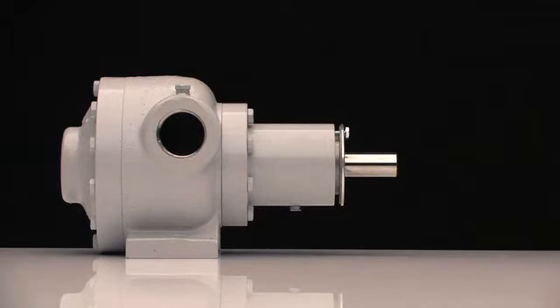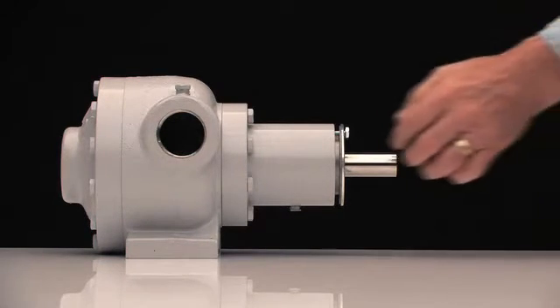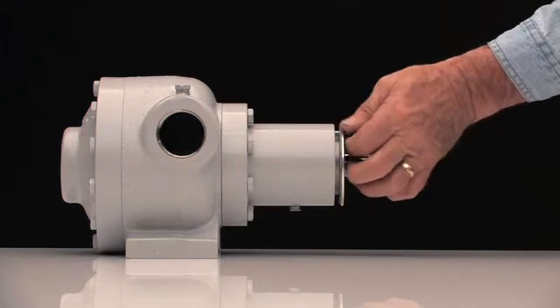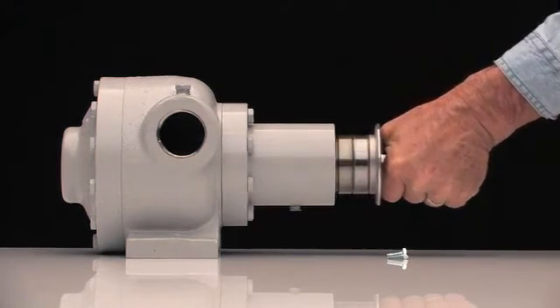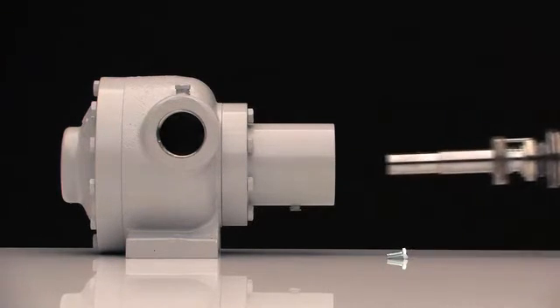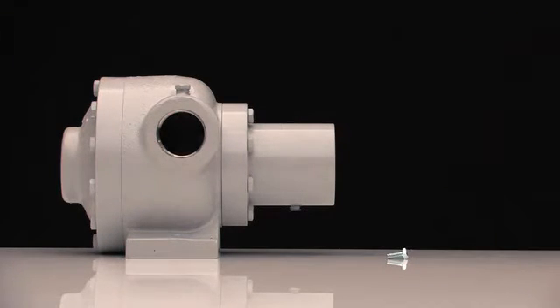Once the bearing retainer plate is removed from the drive shaft end of the pump, the drive shaft is pulled out of the pump and the entire assembly comes out. There are no loose parts to deal with and little chance the seal faces can become contaminated from dirty hands or the environment.